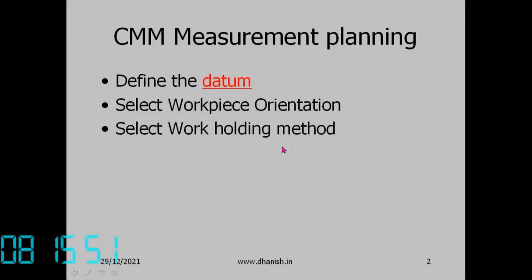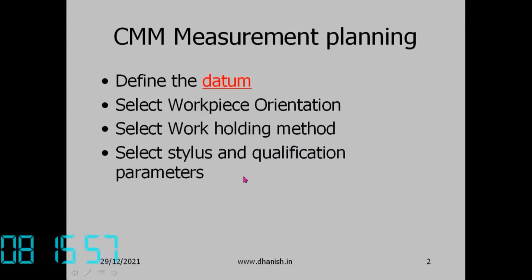Select the work holding method — how will you hold the workpiece. Then we have to select the stylus and qualification parameters: what is the stylus diameter, stylus extension. When qualifying the stylus, we run it at a certain speed using a calibration sphere, taking several points to calculate the position of the stylus and its diameter.